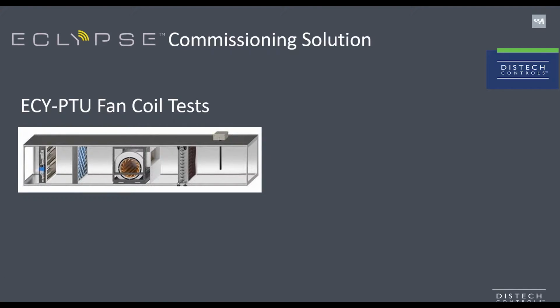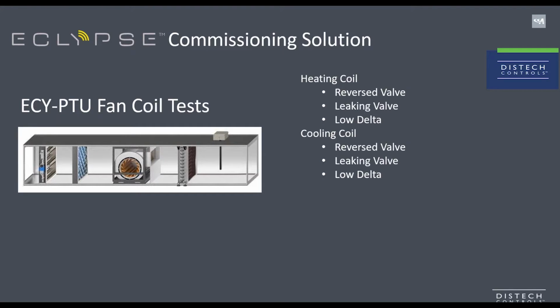For sure. Your ECLYPSE ECY PTU series controllers are now shipping from the factory with the ability to run a series of functional tests at the edge. Provided that your system is equipped with a discharge temperature sensor, you can run tests and generate reports on the following pieces of equipment. The system will automatically detect if your heating coil valve is reversed, leaking, or if the coil is not delivering enough heat. The cooling coil test will provide you with the same information as the heating coil.